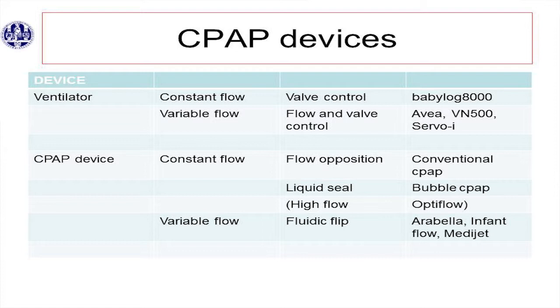Then the CPAP devices can be divided between constant flow and variable flow. Constant flow is the conventional way — mostly abandoned now. Most use bubble CPAP or the fluidic flip devices: that's the infant flow driver, MediJet, Arabella. They have different mechanisms: the liquid seal and the fluidic flip — I'll come back to that. Did I forget any device that you use? Leone Plus — that's a ventilator, and it has fluidic technology. And Stephanie. These were just examples; there are many ventilators and many more CPAP devices. The funny thing is, because I have these examples from reviews, Stephanie's never mentioned, and neither is the Leone Plus. So there's work to do for you guys.